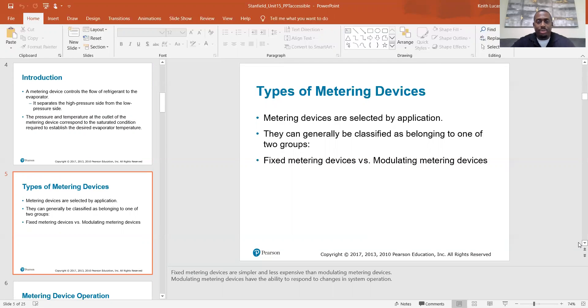There are different types of metering devices, and they're selected by application. They can generally be classified as belonging to one of two groups: fixed metering devices and modulating metering devices. Fixed metering devices are simpler and less expensive than modulating metering devices. Modulating metering devices have the ability to respond to changes in system operation — basically load changes.